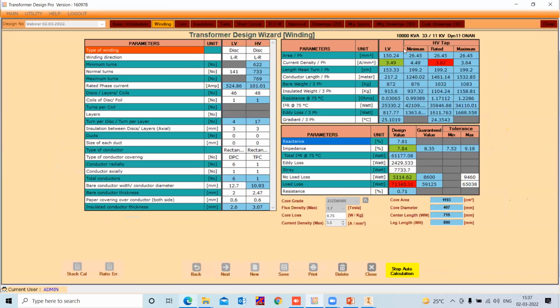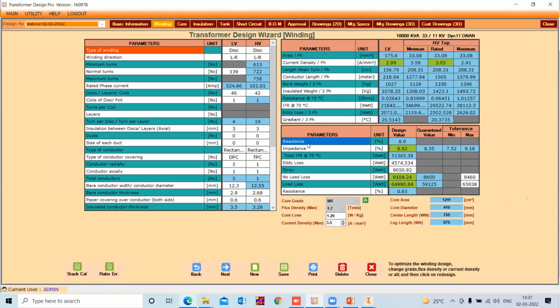Now you can see on your right side top corner, there is 10 MVA, 10000 kVA, 33 by 11 kV, DYN 11, and ONAN, oil natural, air natural. Below that, the area per phase, current density, length mean turn, conductor length, bare weight, insulated weight, resistance at 75 degrees Celsius, I square R losses, eddy losses, gradient. Thereafter, in the next table, you can see parameters like reactance, impedance, total I square R losses, eddy losses, stray losses, no load loss, and the resistance.